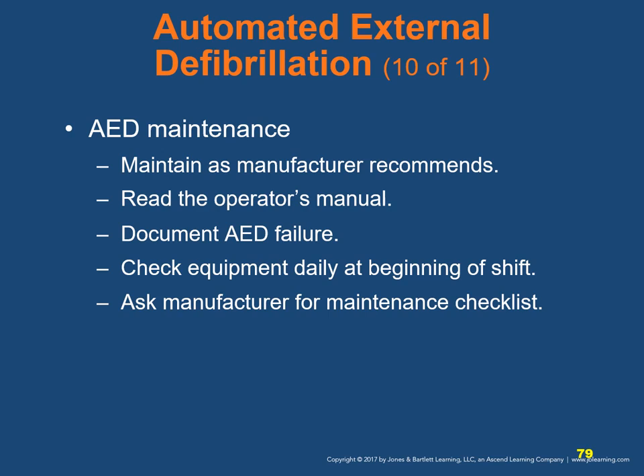The 3 most common errors with certain AEDs in terms of their performance is the machine might not detect a fine ventricular fibrillation reading. In other words, the patient's in VFib, but it's so fine or faint that the machine does not recognize it very well or at all, and therefore doesn't shock. Another error that can occur with certain AEDs is applying the AED to a patient who is moving, squirming, or being transported. The machine can't discern body movement from heart rhythms because obviously your muscles run on electrical activity as well. So it just can't discern body movement from the heart rhythm itself.